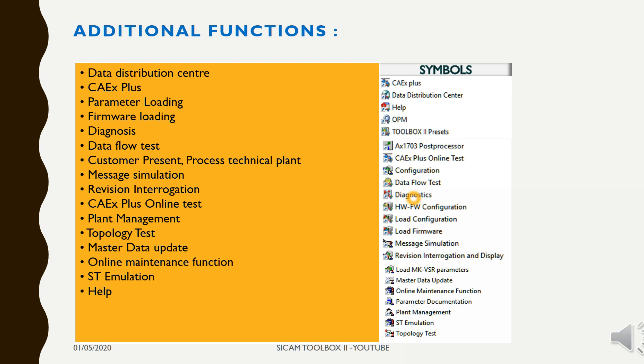Data flow test is used to ensure data is output for the defined station customer, where you can define the identification of the customer. Message simulation allows you to simulate messages within the automation unit. Revision interrogation is used to check the firmware within the automation unit and engineering station. CAEx Plus online test is used for testing purposes during commissioning — you do not require any keys to access this module. Plant management is where the database of the entire project is managed, including customer parameters and others. Topology test is used to identify correct data receiving and sending within stations.